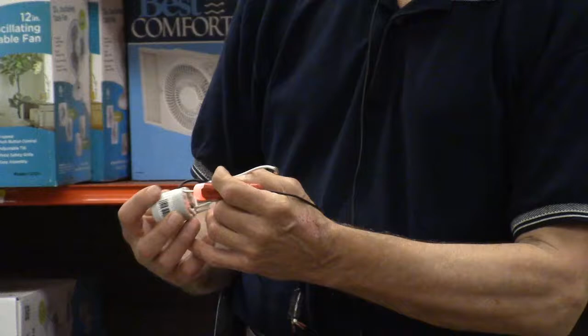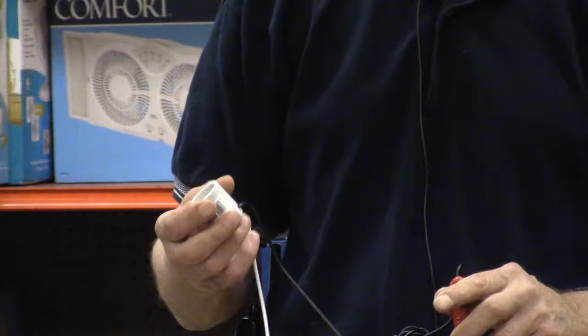Can I also test a light bulb socket? Sure. A lot of times outside, because of corrosion, you can get light bulb sockets that go bad. The corrosion takes place where this rivet is, okay? And if this thing is sitting in moisture, you can get corrosion between the wire and the inside contacts. It's a very common thing on outdoor light fixtures, and you have to replace the sockets.